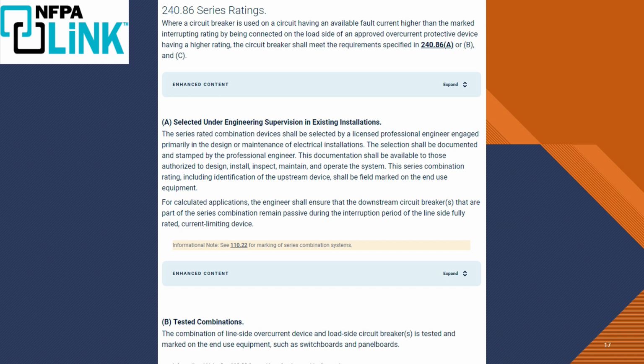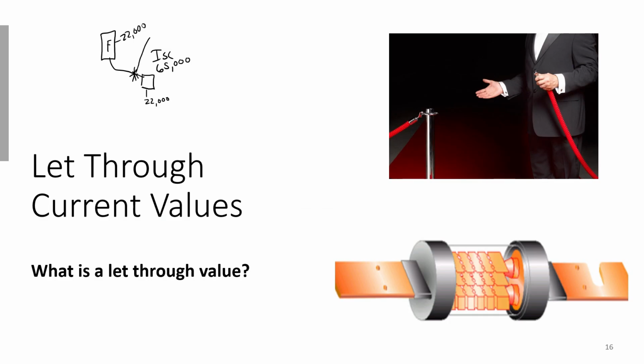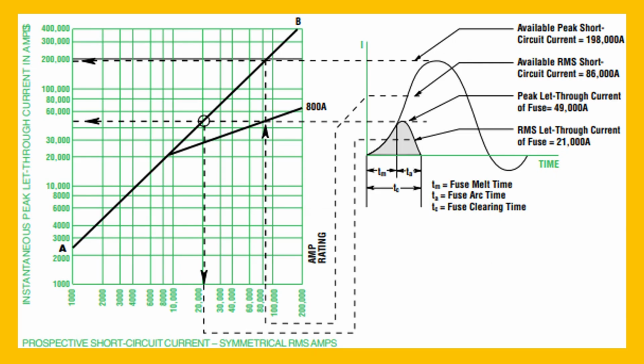So I don't want to say that they can't do it. I want to point out some confusion about when they can do it. I say they, the engineers, when an engineer can use a let-through current, because the short circuit current rating in this example is still 65,000. And there's nowhere in the National Electric Code that says I can use a fuse let-through value in lieu of a short circuit current rating or value. I just can't do it. There's no code that allows these things to be. And I just wanted to clarify that while we're doing this quick little video.